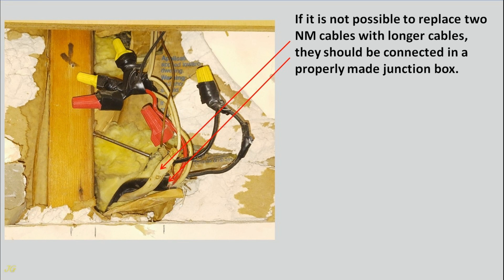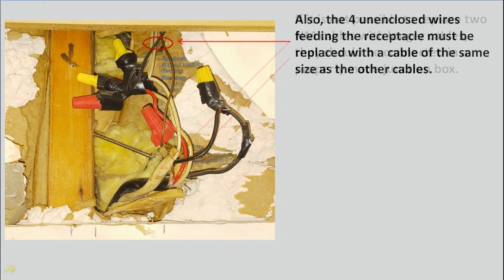If it is not possible to replace two NM cables with longer cables, they should be connected in a properly made junction box. Also, the four unenclosed wires feeding the receptacle must be replaced with a cable of the same size as the other cables.